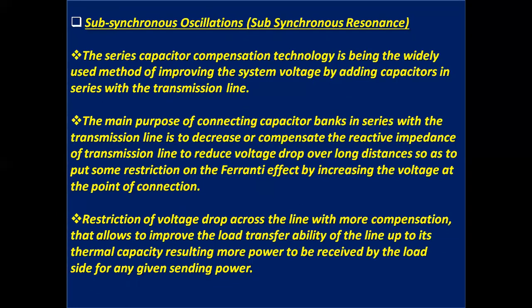Now, what are sub-synchronous oscillations? That is sub-synchronous resonance. Series capacitor compensation is a widely used method of improving the system voltage by adding capacitors in series with the transmission line. The main purpose of connecting capacitor banks in series with the transmission line is to compensate the reactive impedance of the transmission line, to reduce voltage drop over long distances, so as to put some restriction on the Ferranti effect by increasing the voltage at the point of connection.